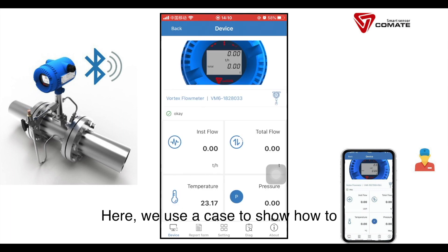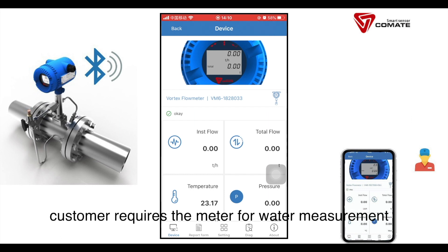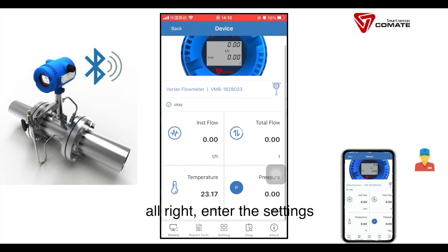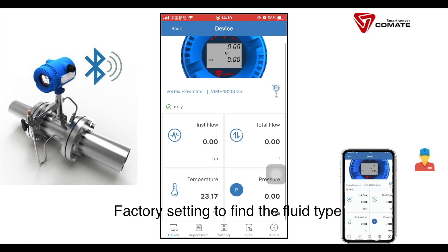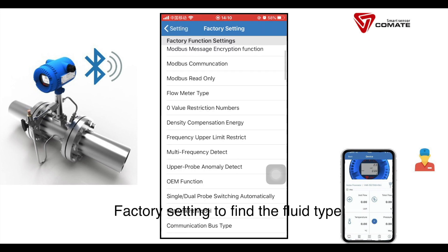Here we use a case to show how to proceed with the settings. The customer requires the meter for water measurement, with output mass flow from 0 to 4000 kg per hour using 4 to 20 mA. Enter the settings, go to factory setting to find the fluid type.